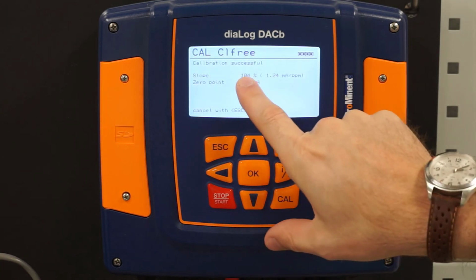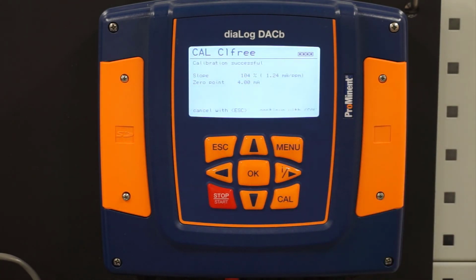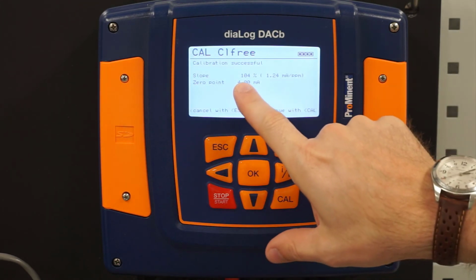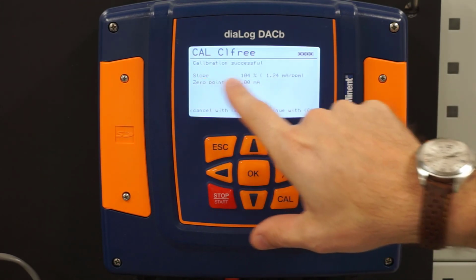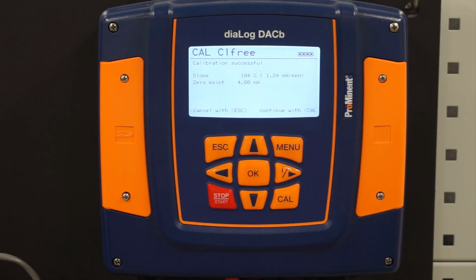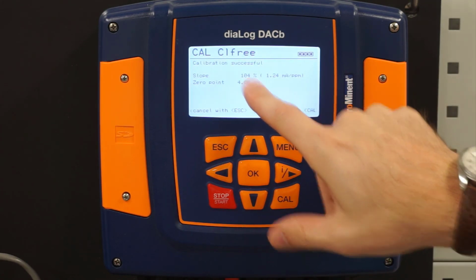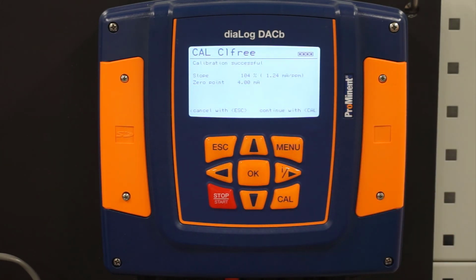And you can see our slope is a little bit above 100%. Same thing with this one. I'm going to look at my slope. That's my important thing. It will let me calibrate down to 20%. So if I pay attention to this number, I should be able to get an idea of when I need to change my electrolyte and membrane cap. So once I start approaching 20%, I better have a membrane cap and electrolyte on hand to do that maintenance.